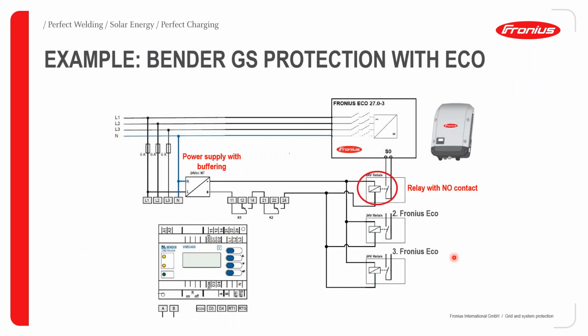Taking a look at how this is implemented, we're going to be looking at an SLD, that's a single line diagram, and for this example, we're using the Bender GS protection with the Fronius Eco. To make it a bit clearer, we have a single line diagram of the contacts of this GS protection device. This is the Bender GS protection device, and this is a single line diagram of its contacts, as indicated by my pointer. Basically how the contacts operate, for every relay, we have three contacts, which is the common, the normally open, and the normally closed contacts. In this case, terminal 11 is the common, terminal 12 is the normally closed contact, terminal 14 is the normally open contact, as can be seen.